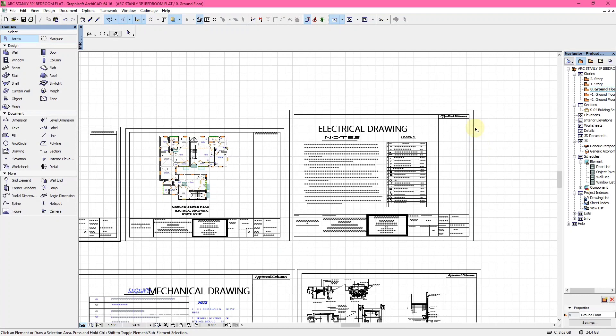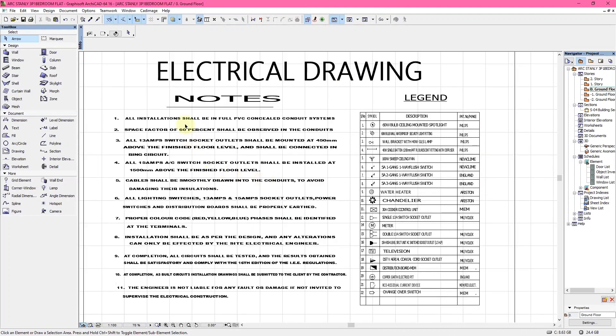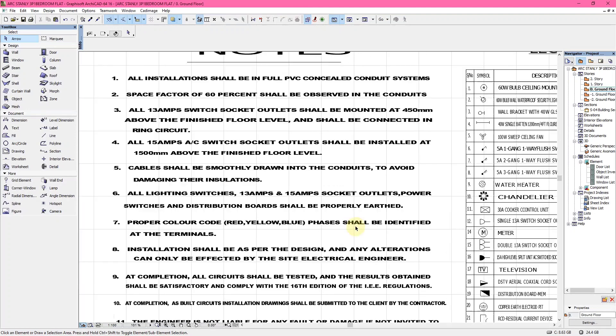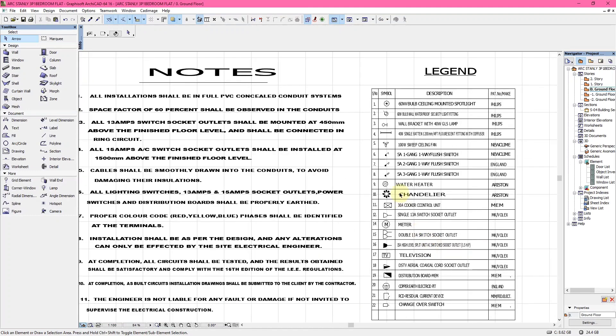Let's start from electrical drawings. This first page is what's called the legend. It shows the notes on the electrical drawing — some detailed notes regarding the drawing. For example: all installation shall be in full PVC concealed conduit system; a space factor of 60 percent shall be observed in the conduit; all 13 amp circuit outlets shall be mounted 450mm above the finished floor level and shall be connected in ring circuit. The last note states the engineer is not liable for any fault or damage if not invited to supervise electrical construction.